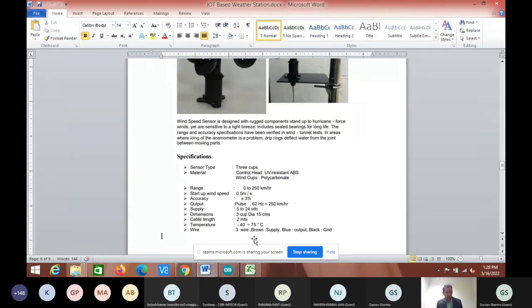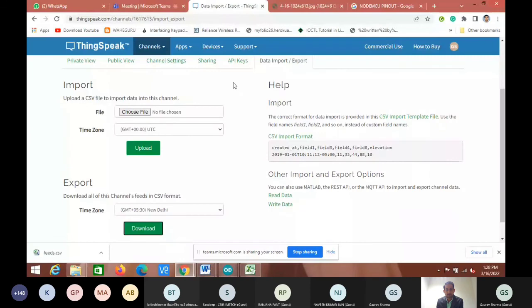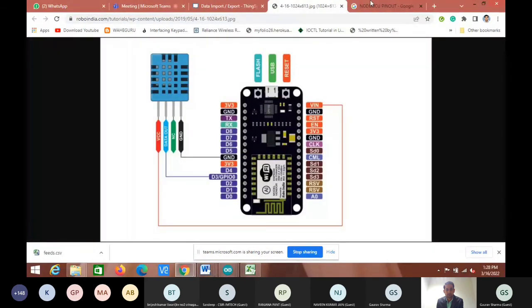So the temperature on the pre-calibrated meter will change, like going from 10 degrees to 15 degrees, and your sensor is giving you values from 200 to 300. You note down those values, taking 3 or 4 updated readings, and then put them into the linear equation. I'll show you how the linear equation helps us to calibrate.